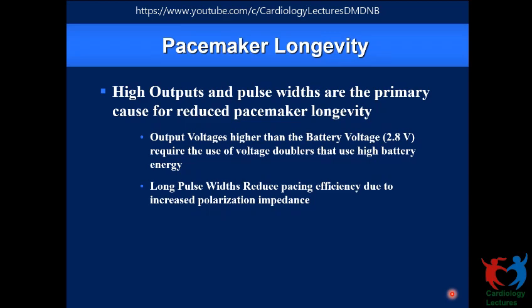At the same time, when you're increasing the pacing output to twice the threshold, there is a risk that you will drain the battery a lot. So if needed, most of the time it doesn't make a difference, but you can adjust the pulse width and see the minimum pulse width at which you get a good threshold, and you can double that.